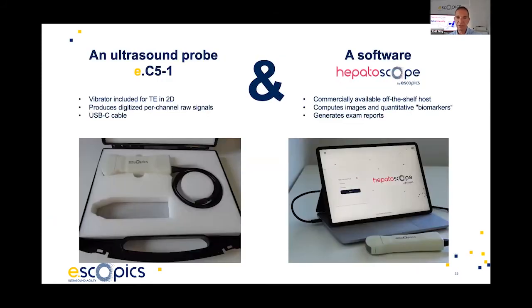This product, the hepatoscope, is made of one probe, as I told you. That's a proprietary probe, and this probe has inside it, at the back, one mechanical vibrator that is able to reproduce the same vibration that exists in the FibroScan probe. It's a 50 hertz vibration. But we are also doing imaging because it's an ultrasound imaging probe, so we are able to extract much more data from the image than FibroScan can do. And there is the hepatoscope software, which is compatible with most high-powered off-the-shelf laptops that exist in the market with GPUs, for example.